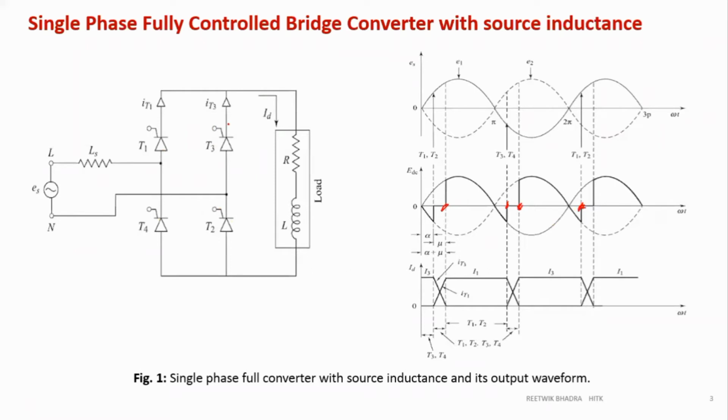And at the point when all the thyristors are on during the transition period, or what we call specifically the overlap period, my voltage is 0. This period is 0. So this angle which is given over here is mu. The first angle over here is alpha, and actually the firing angle is becoming alpha plus mu. So the point where my thyristor starts conducting is actually not alpha but alpha plus mu because of the overlap period. Now what is happening during this period?